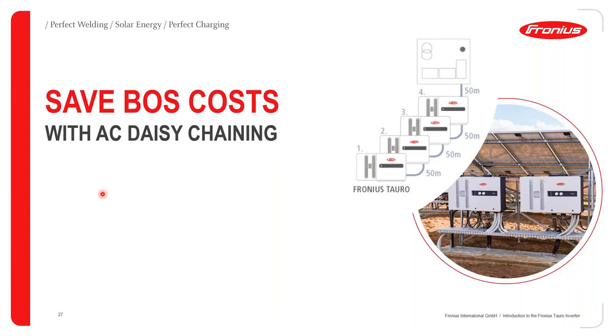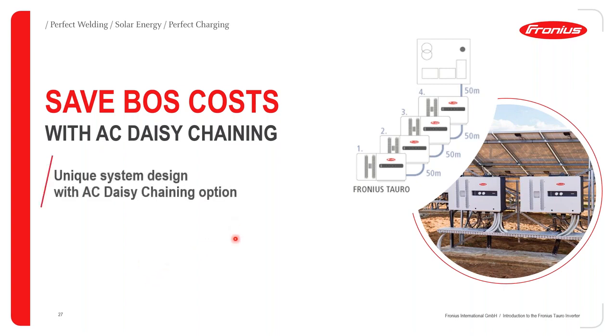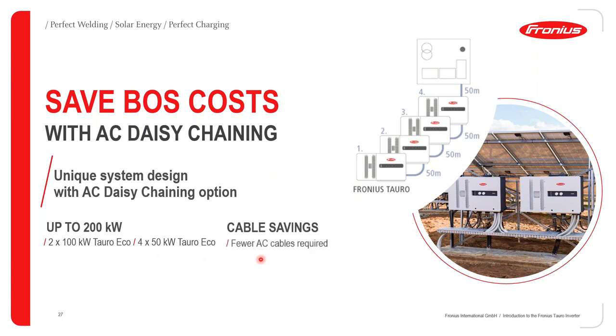Let's continue on how you can realize more savings as far as balance of system components are concerned, with AC daisy chaining. As I've already mentioned, you can have a maximum of 200 kilowatts, and that means using 2 by 100 kilowatt Tauro Eco inverters, or you can use 4 by 50 kilowatt Tauro Eco inverters. The way you realize these savings as far as cables are concerned using the daisy chaining topology is that fewer AC cables will be required overall.